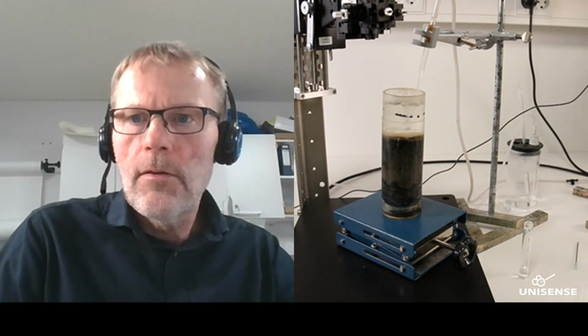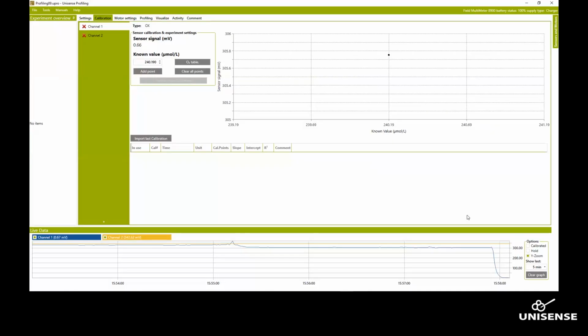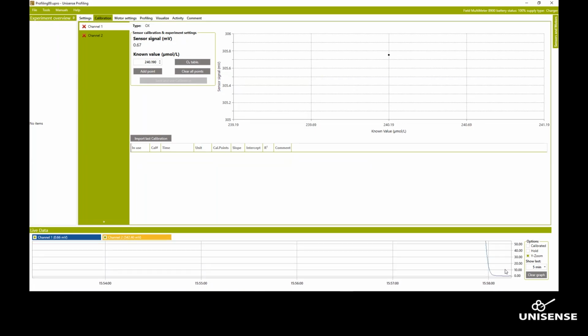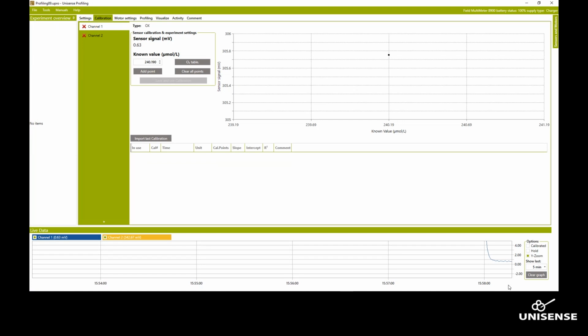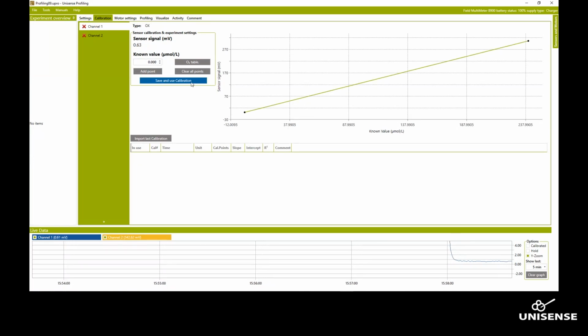And I'll share my screen again so you can see. So now you can see that the signal has dropped a lot and fast. I will zoom in here and see if we are down at a stable level. So it takes a little while to get down to the full response. As I mentioned, we normally talk about 90% response. It's about 5 seconds for a sensor like this, or maybe 3. But now it has stabilized. So I will enter 0 in the known value here, and then click add point. And I now have a 2-point calibration, and I'll save and use the calibration.